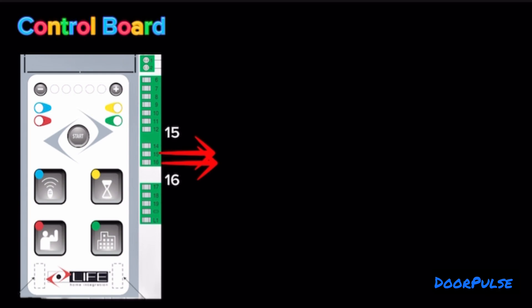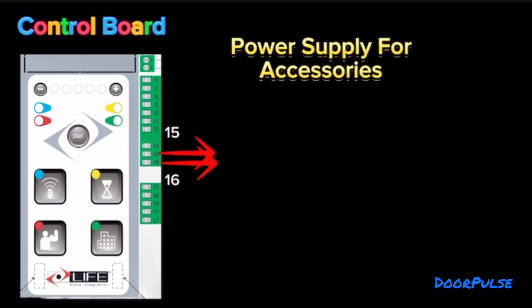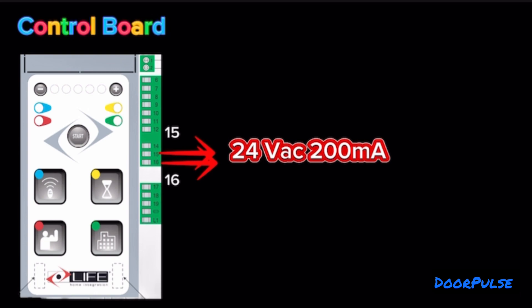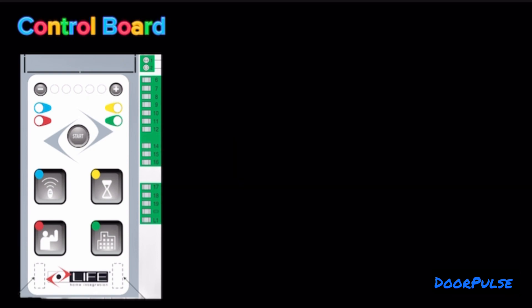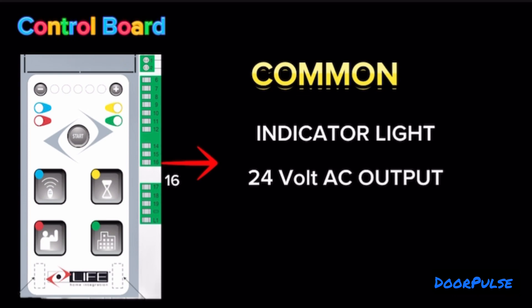Terminals 16 and 15: 24 Volt AC output for powering various devices, 200 mA Max. Terminal 16 is common indicator light 24 Volt AC output.